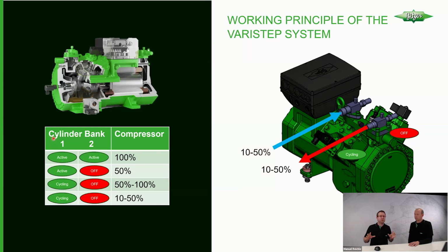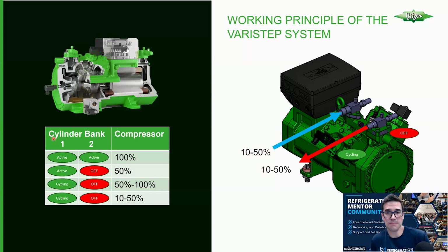We brought the compressor out of that critical situation without making any trouble. This is a function which we tested in 2017, and since then we haven't heard any problems with it, because nobody is really going to recognize that we are overriding the signal.